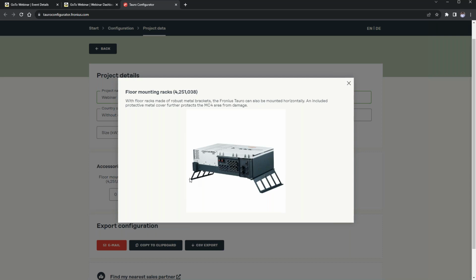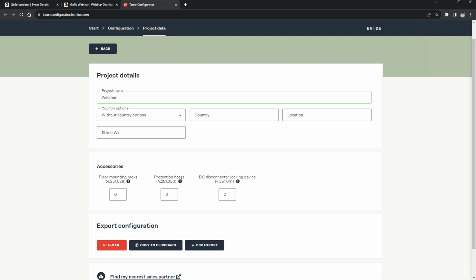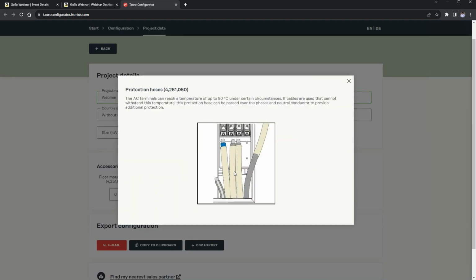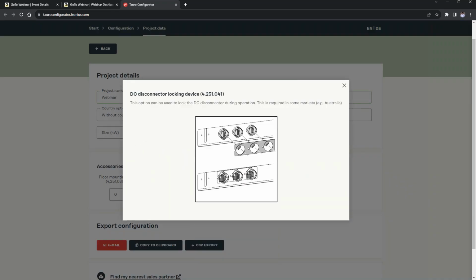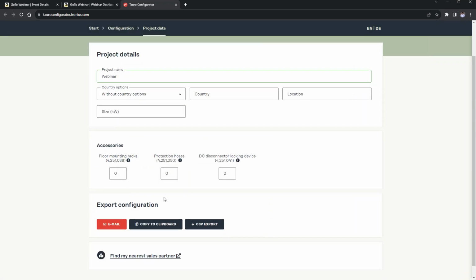So this is how it looks. You would need these floor mount racks to be able to achieve this. So if you need them, you can include them here. Protection hoses are basically to help strengthen the insulation between the cables in terms of temperature coefficients. And then you can also include DC disconnector locking devices to prevent unauthorized operation. And this is actually a normative order in some markets like Australia, for example. So after making your choices, you can go ahead and export your configuration either as an email, copy to clipboard, or as a CSV file.